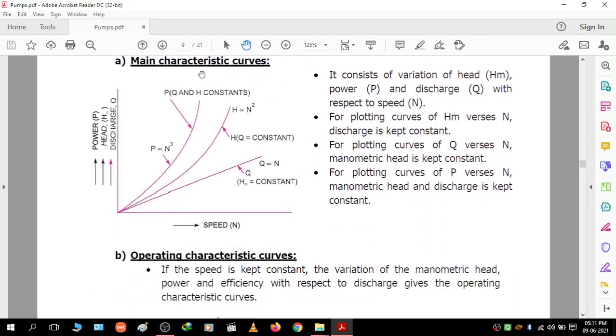The main characteristics curve is a graph of speed against power, head, and discharge. It consists of the variation of head, power, and discharge with respect to speed. For plotting curves of manometric head versus speed, discharge is kept constant. For plotting curves of discharge versus speed, manometric head is kept constant. For plotting curves of power versus speed, manometric head and discharge are kept constant.